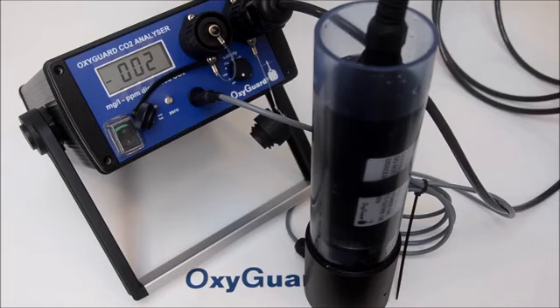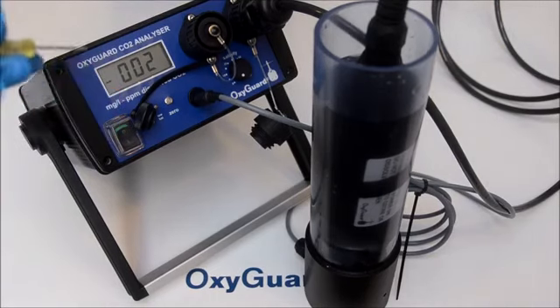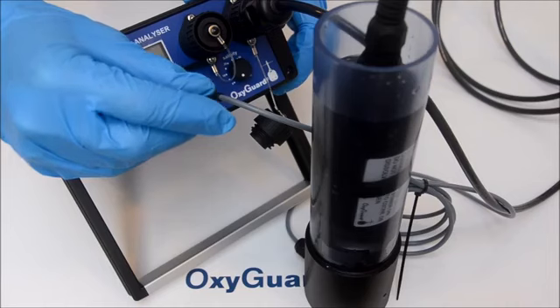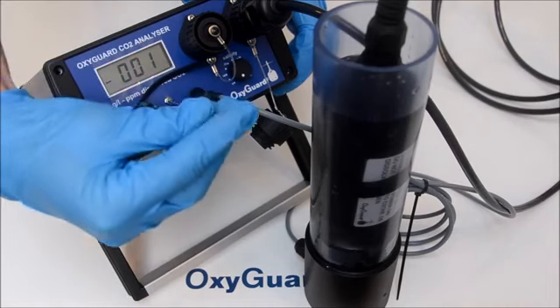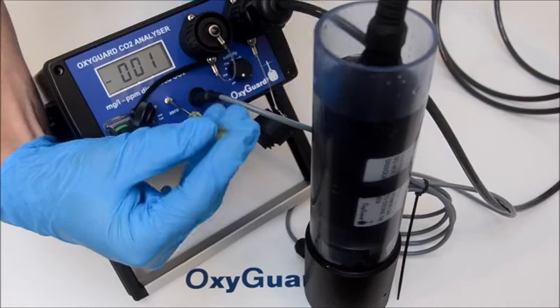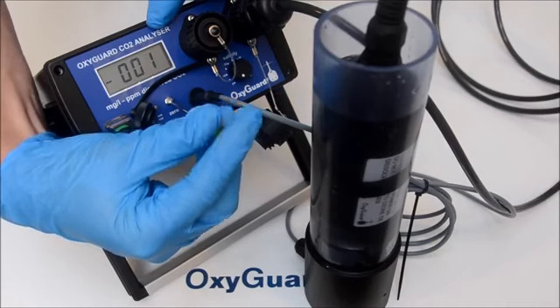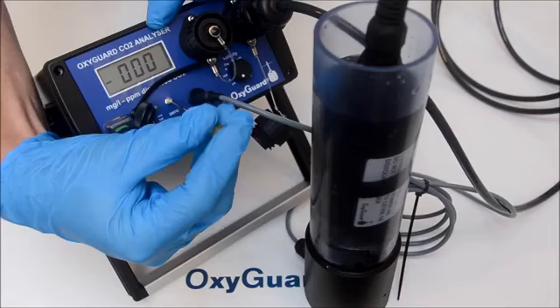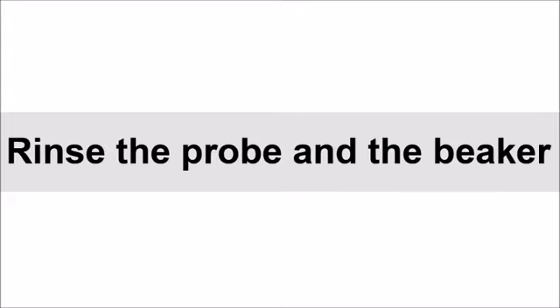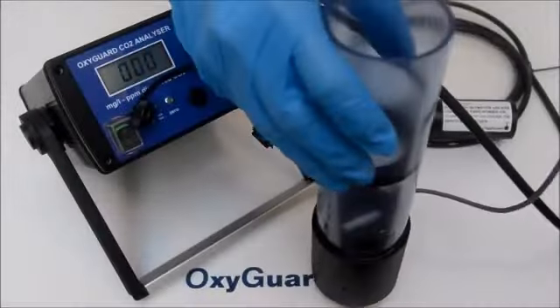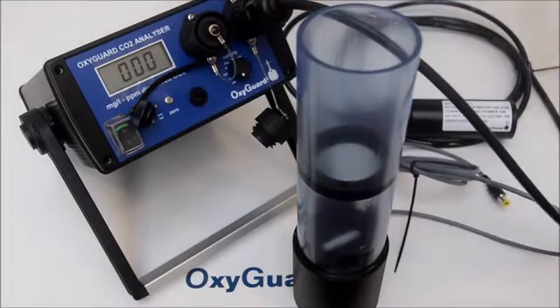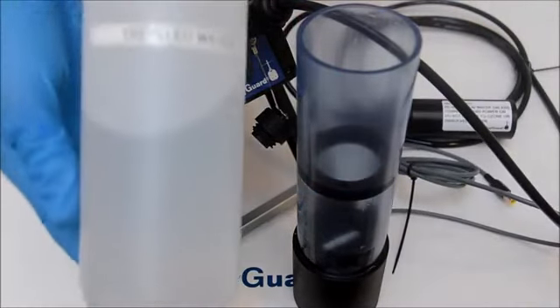When the reading is stable, you can adjust the zero adjustment until it displays 0. Stop the stirrer. Empty the beaker, rinse the probe and the beaker with the distilled water. We are now ready to proceed with the calibration procedure. Pour some distilled water in the beaker. The water should reach the upper part of the black ring in the middle of the beaker.